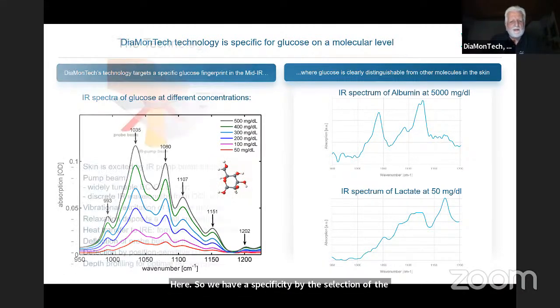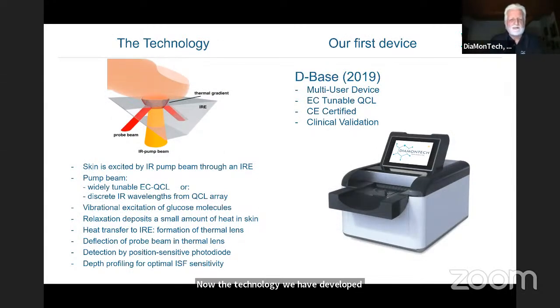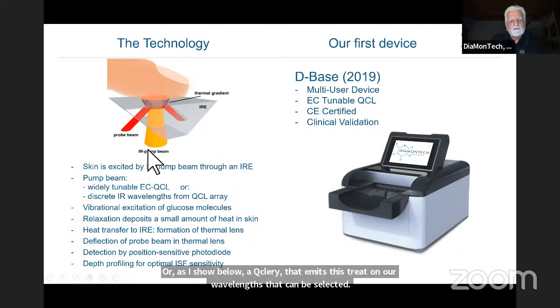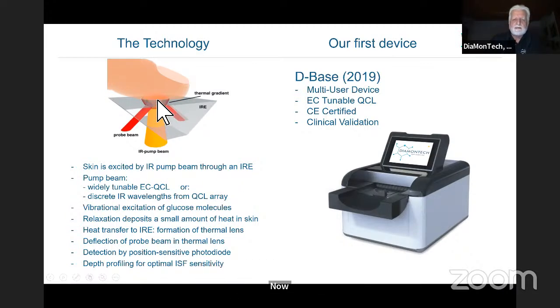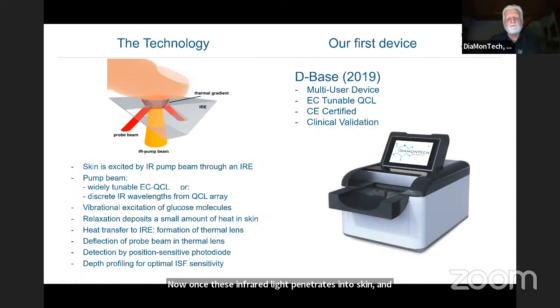Now, the technology we have developed is a photothermal technology. Basically, you see the principle here on the left side. We use a quantum cascade laser to pump infrared light through this internal reflection element, IRE, into skin. This can be either a widely tunable external cavity QCL, or, as I show below, a QCL array that emits discrete IR wavelengths that can be selected. Now, once this infrared light penetrates into skin, and the penetration depth is about 80 to 100 micrometers, so deep enough to reach interstitial fluid, it leads to a vibrational excitation of the glucose molecules.